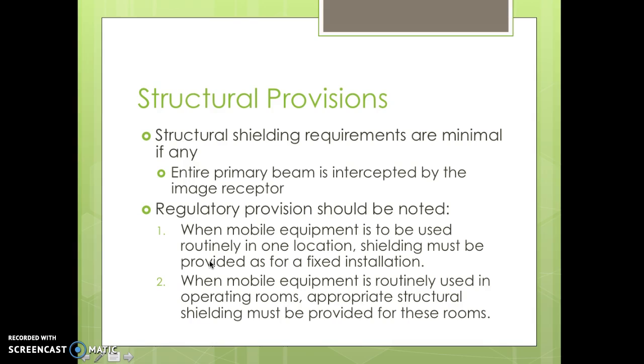Okay, so structural provisions. Structural shielding requirements are minimal, if any, since the entire beam is pretty much intercepted by the image receptor. Regulatory provisions should be noted, though. When mobile equipment is being used routinely in one location, shielding must be provided as for a fixed installation. So if you're just using it in the ER over and over in the same place, you have to actually provide the protection like you would if it was installed in that room. When mobile equipment is routinely used in operating rooms, appropriate structural shielding must be provided for these rooms.